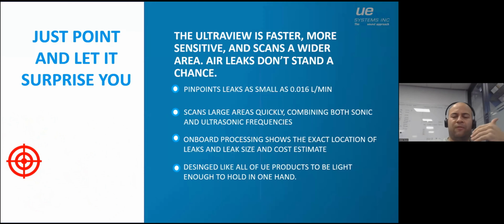So you can do a very quick scan in the factory. You just walk around, and when you see something on the screen, you know, hey, there's a leak. I will get a little closer to confirm where it is and save the snapshot. You also see it pinpoints leaks as small as 0.016 liter per minute. So it's a very low level, and that makes it interesting for vacuum too. With a vacuum leak, the turbulence mostly goes inside the equipment, but with the camera you can still find vacuum leaks from a pretty far distance.